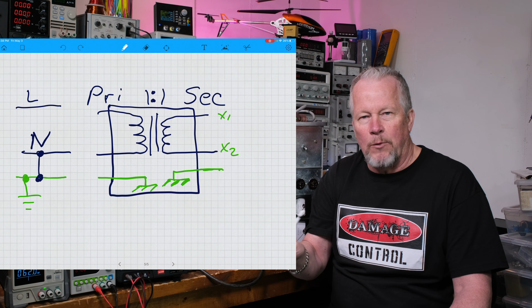Okay, so what you do is you come and say, let's bond it. You recreated this bond thing. So now instead of X2 and X1, now we'll call this line a neutral. It's a different line or neutral, so maybe call it line 2 and neutral 2. Okay, so now if line 2 touches this, we pop a breaker. Let's say we have a fuse or a breaker inside this transformer, or even on the outside on that line. So now it pops a breaker.